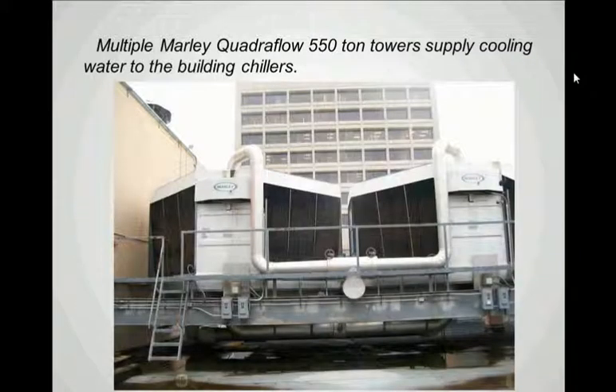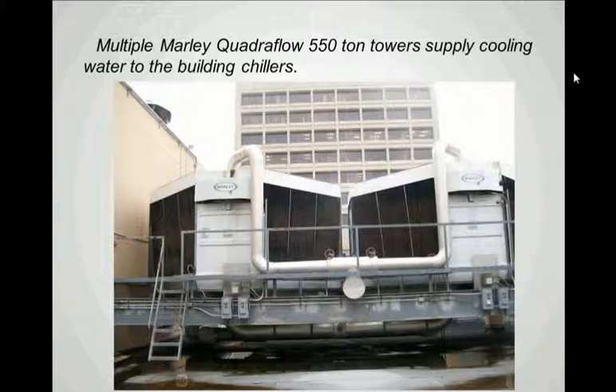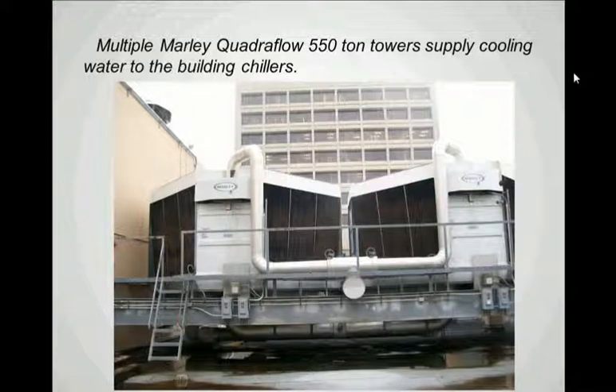Cooling towers come in all different sizes, shapes, and designs. Here's another Marley design — it's called a Quadriflo tower. These are much larger, 550-ton towers that supply cooling water to the building chillers. But the design concept remains the same: we pump the water up to the top of the cooling tower where it flows down through the cooling tower fill. The fans located on top of the tower pull air in and through the fill, where it comes into contact with the water to remove the waste heat being picked up from inside the building.